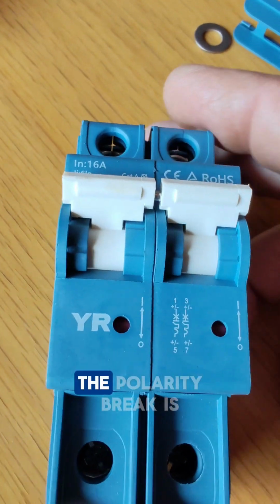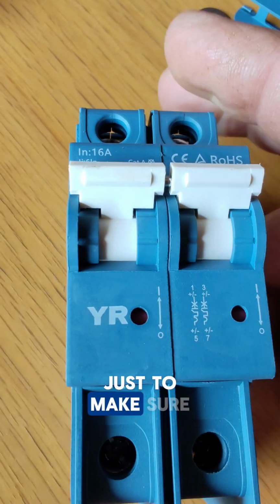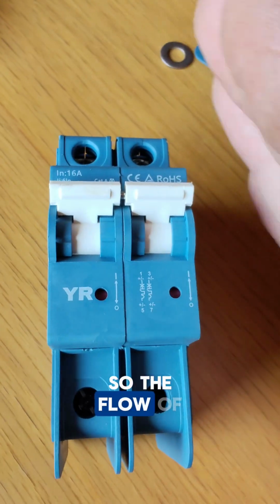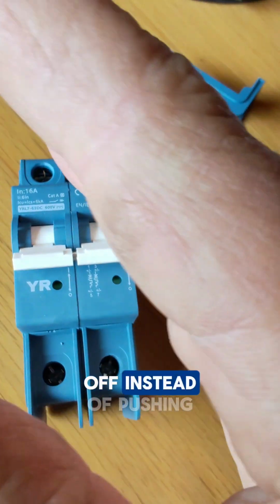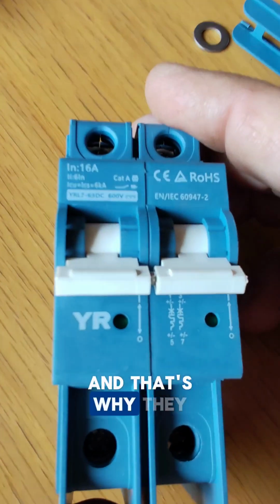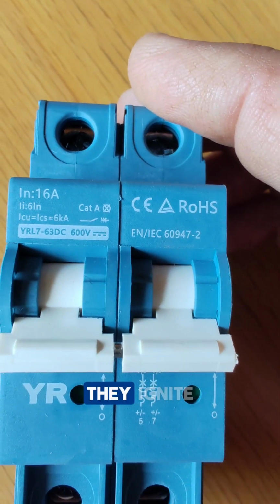The polarity breakers, just to make sure again, regarding the flow of the current: if you switch it off, instead of pushing the arc away, it will push it inwards, and that's why they are so dangerous and they ignite. Now remember, it's wired in reverse polarity, so instead of trying to extinguish the arc, it's going to have a failure. And you can see very quickly we have a major issue.